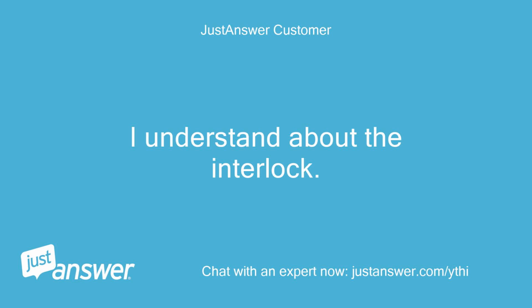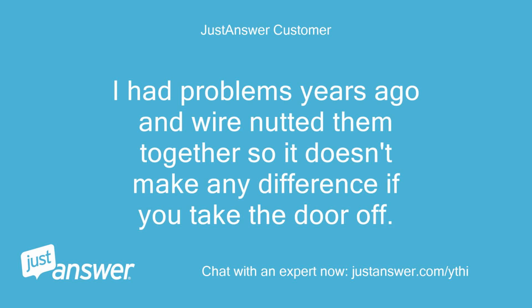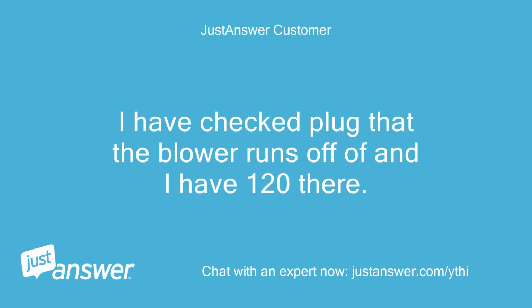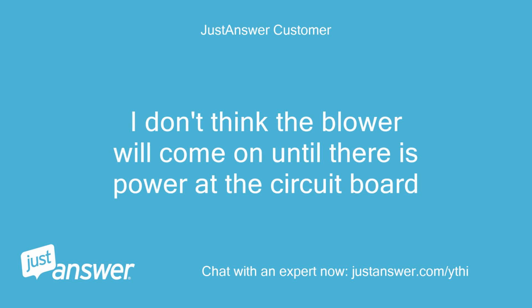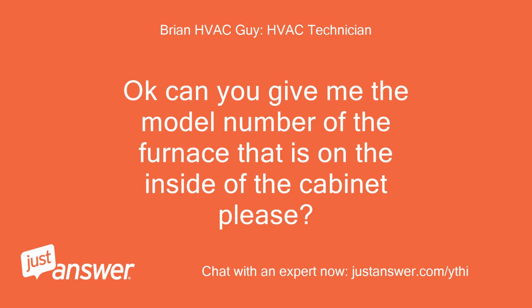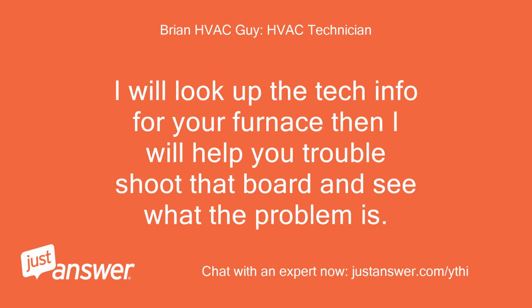I understand about the interlock. I had problems years ago and wire nutted them together, so it doesn't make any difference if you take the door off. I have checked the plug that the blower runs off of and I have 120 there. I don't think the blower will come on until there is power at the circuit board. Okay, can you give me the model number of the furnace that is on the inside of the cabinet, please? I will look up the tech info for your furnace, then I will help you troubleshoot that board and see what the problem is.